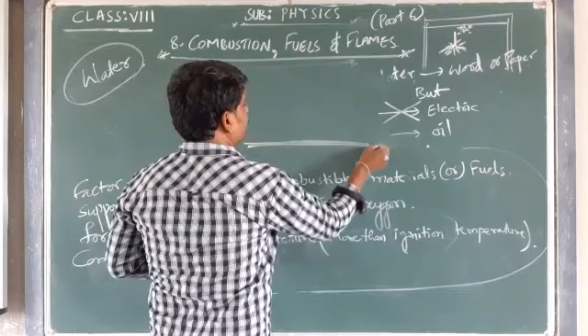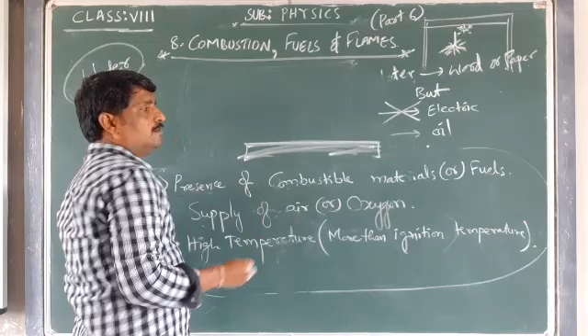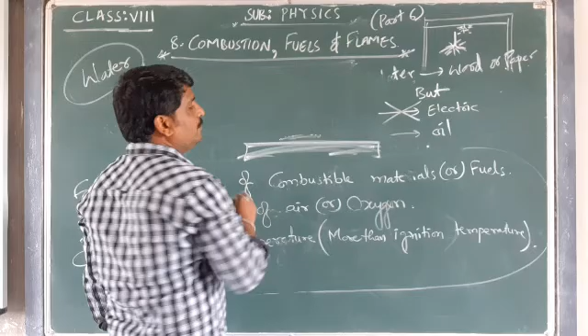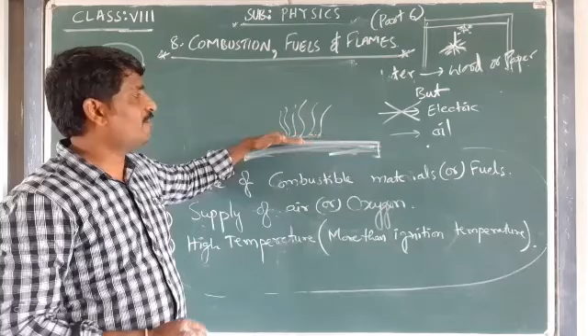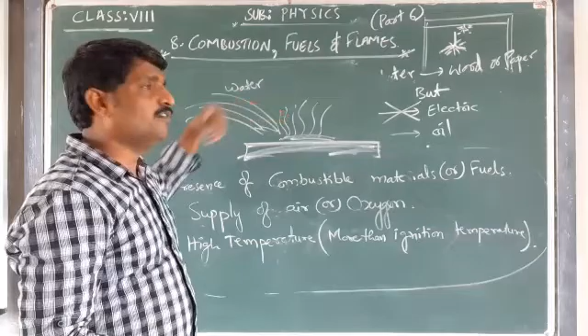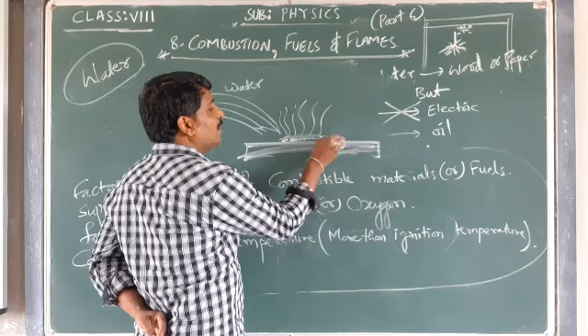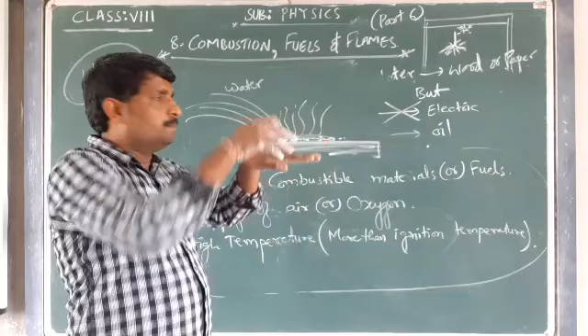assume this is a floor, and this much area is oil. If this oil is on fire, for example some petrol or some kerosene is on fire on the floor, and whenever we are pouring some water, this should be in a huge quantity, to control this oil on fire, the water, due to heaviness, will settle on the bottom of the oil, where the oil will be on the top. Even though we are pouring, the water goes and settles on the bottom of the oil, and the oil will be on the top.